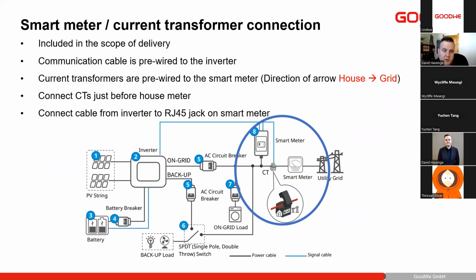The next is the smart meter installation. It's very important to install the smart meter correctly. So the inverter does have the communication pre-wired. That cable is 15 meters long. Should the smart meter be further away than that 15 meters, it's fine. You can replace that cable entirely. So you'll replace the communication cable.